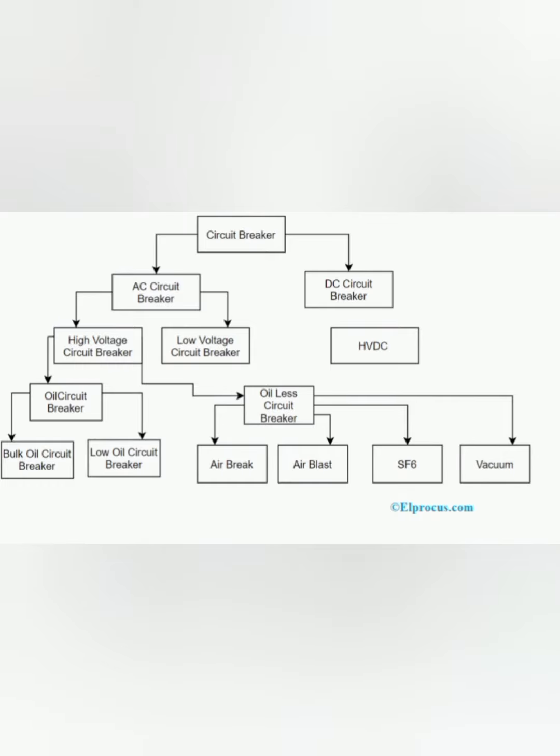Nowadays we are using this SF6 and vacuum circuit breaker. SF6 will be used in the higher voltage levels of your substations also. In SF6 itself, we can easily divide the SF6 breaker as single interrupter, double interrupter, four interrupter, like that. According to our substation level we can use those SF6 types.